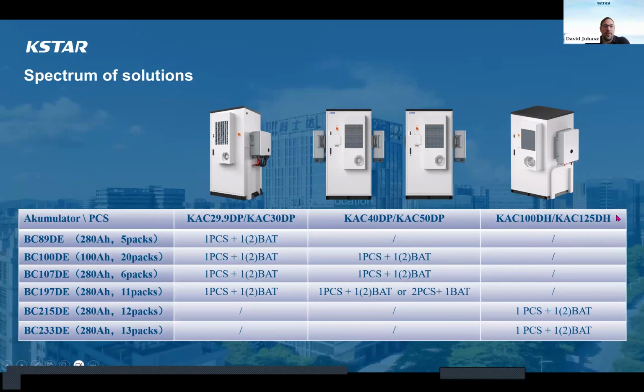So regarding the configurations, if we choose one system, we need to build it with the same storage capacity for each cabinet. It needs to be everything the same. So you cannot put together the 215 with the 233. If you want to reach a bigger storage capacity, you have to use only the 233.